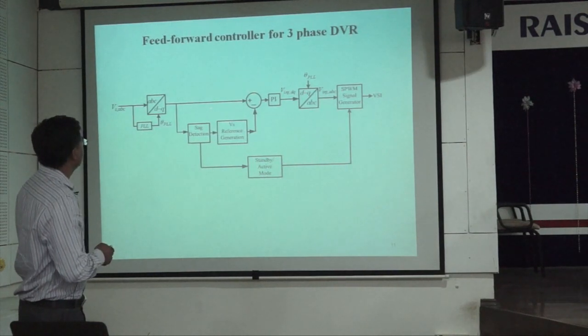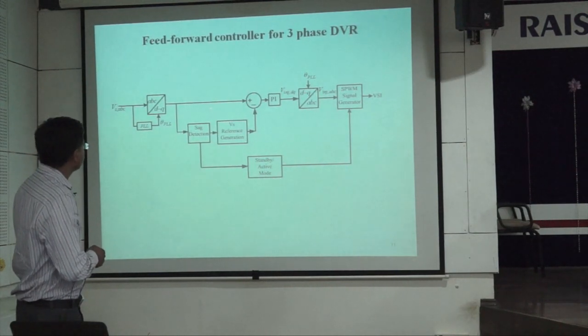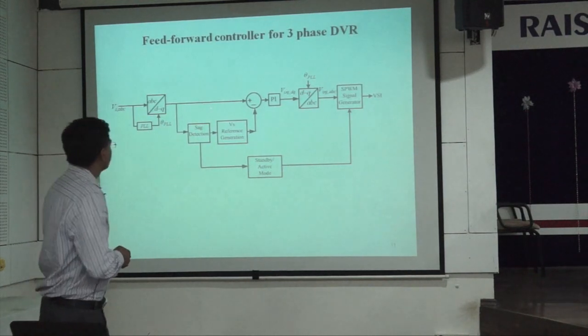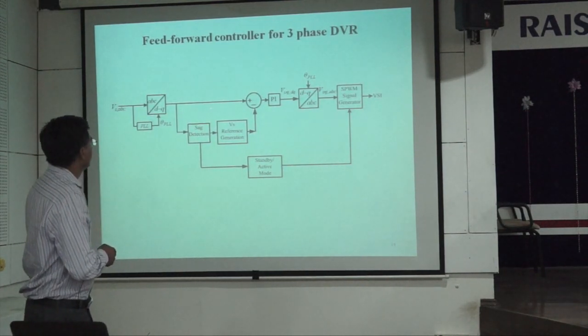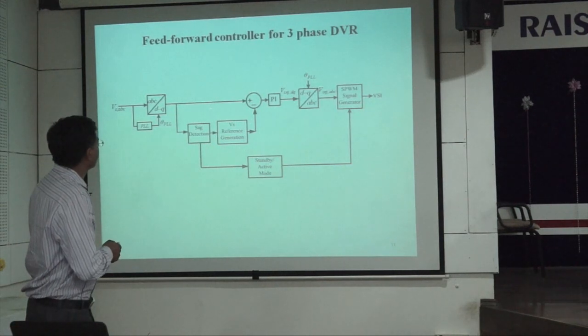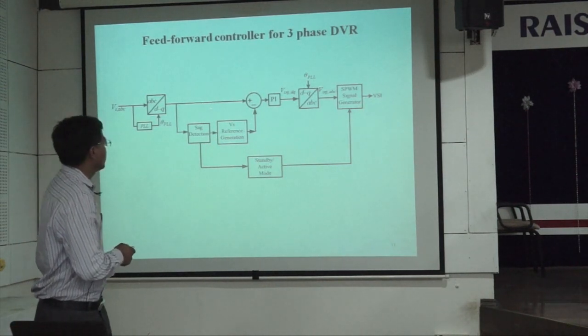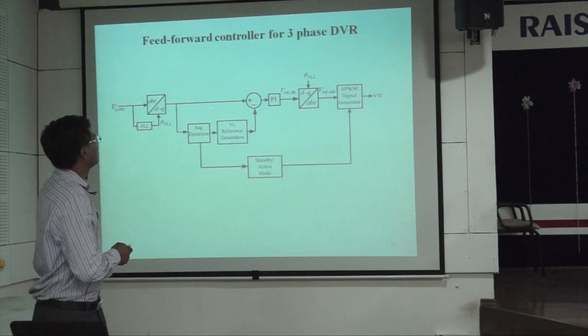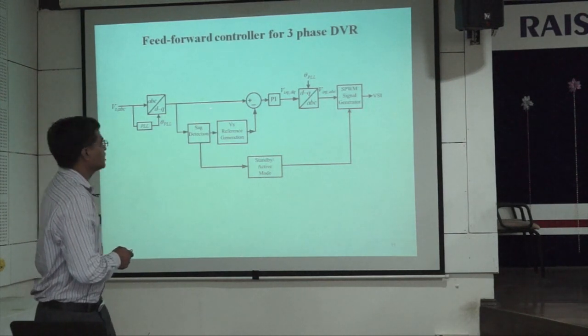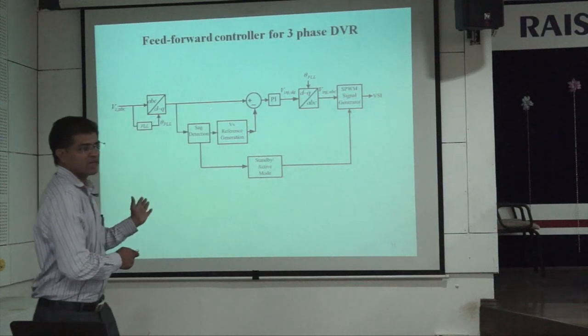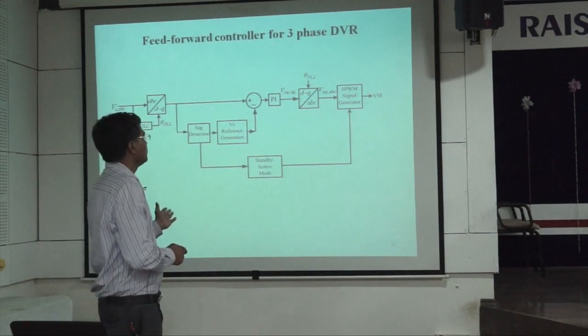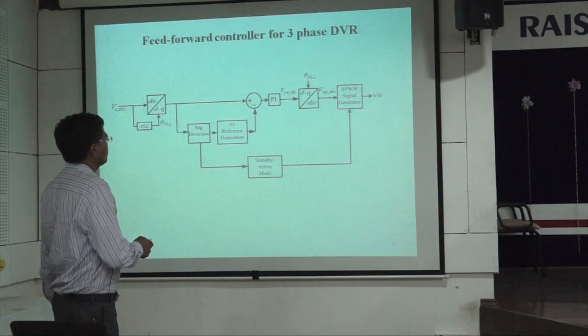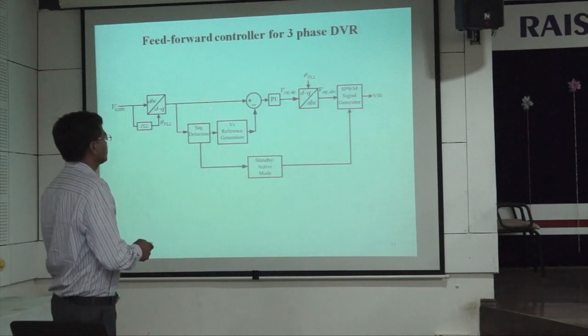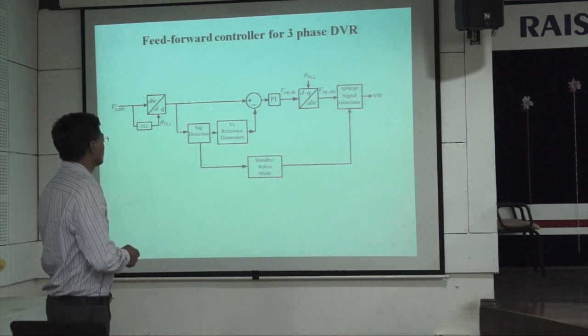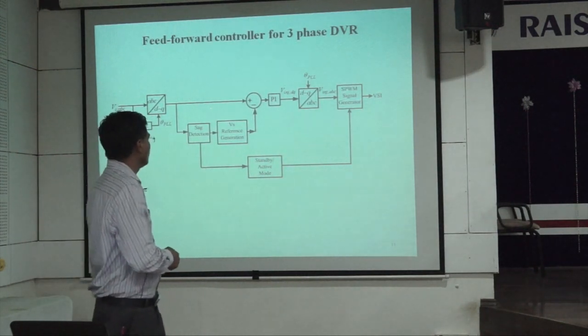So whenever the sag detector detects the signal, the reference supply voltage is generated, and it is compared with the actual voltage. The PI controller injects the error, and these errors are converted from DQ to ABC, meaning the instantaneous value. That instantaneous reference sinusoidal value is compared with the triangular waveform, that is, the SPWM technique is being used, and given to the VSI. The DVR can be controlled either in standby mode or active mode.